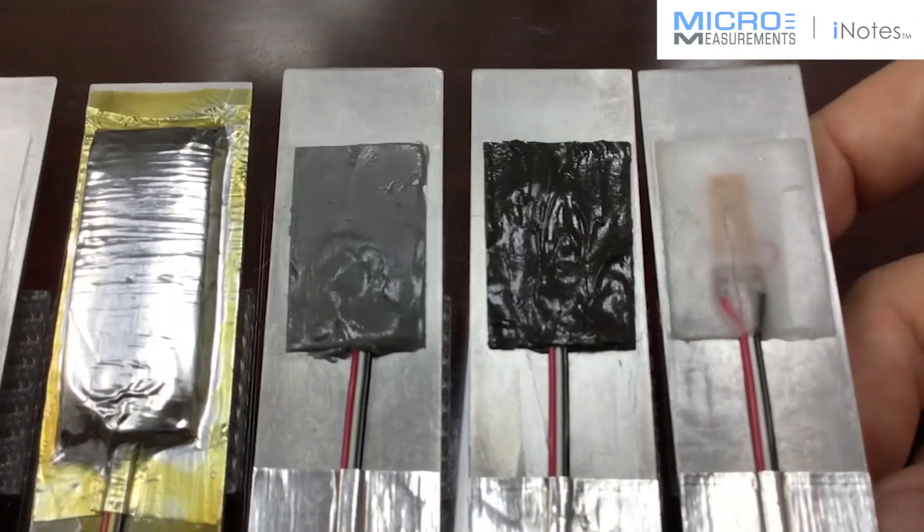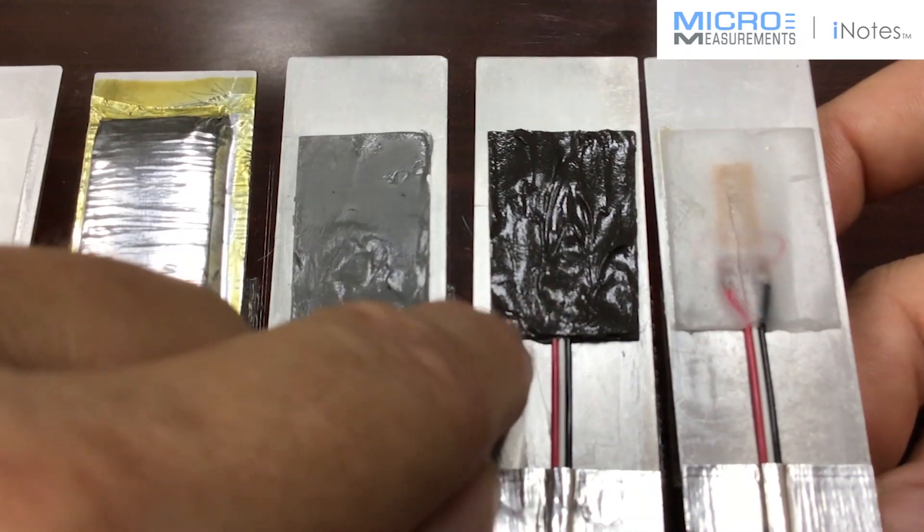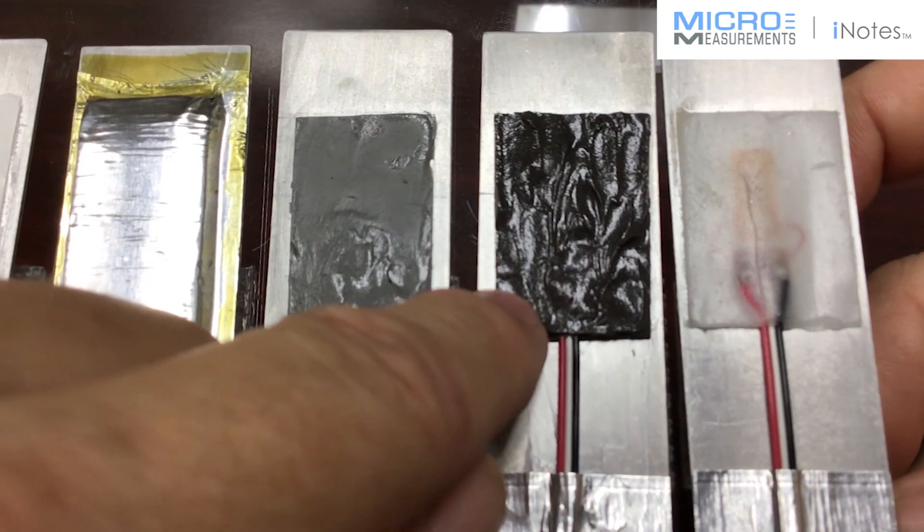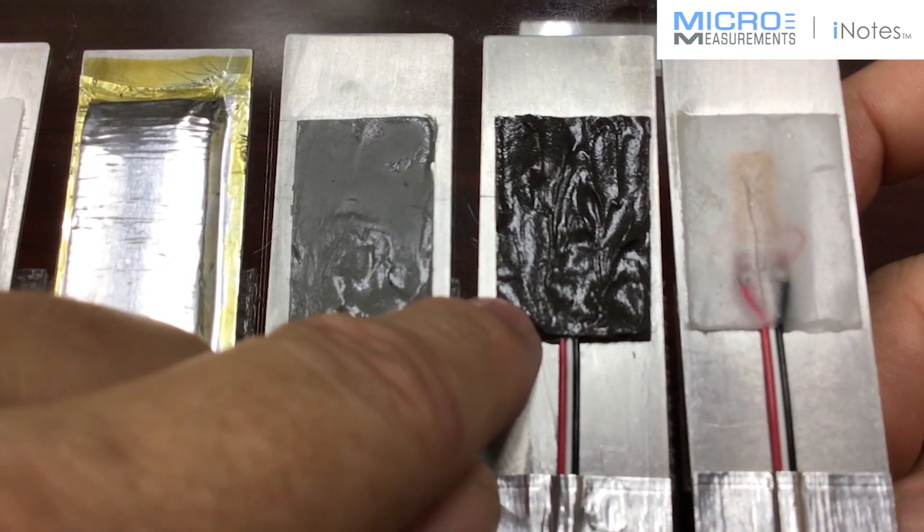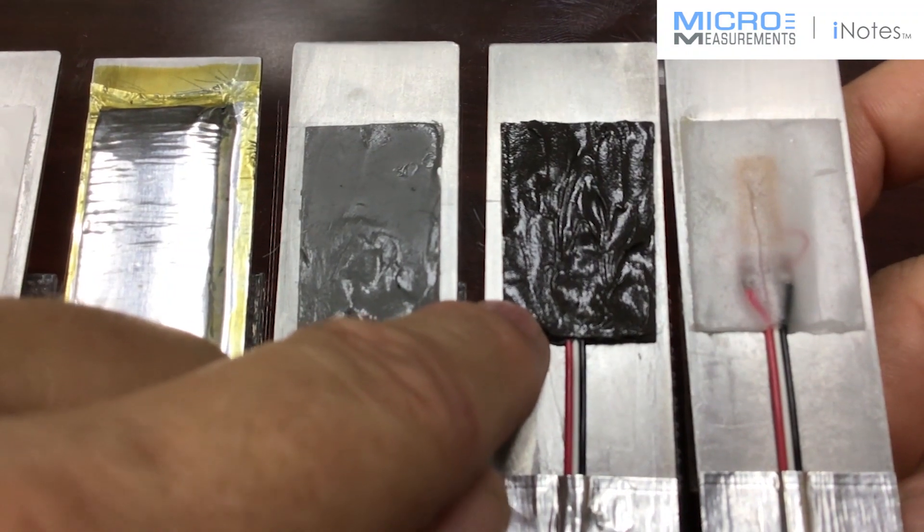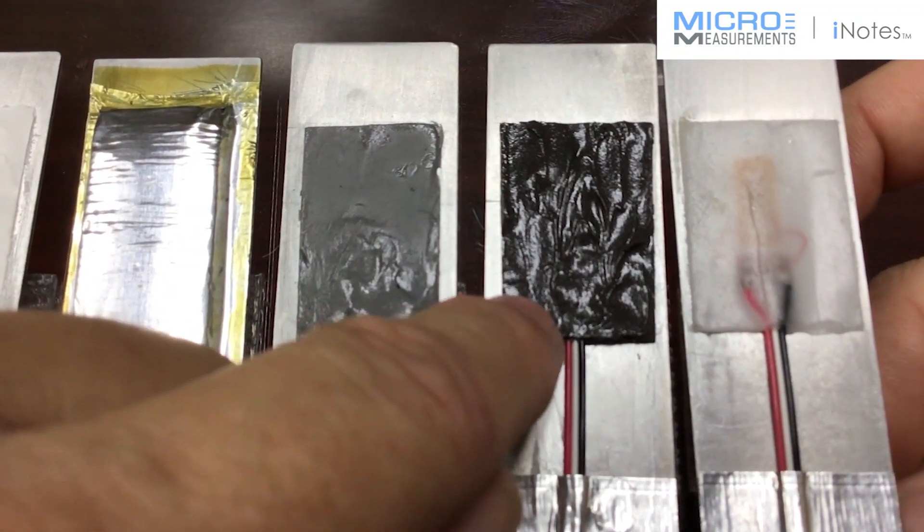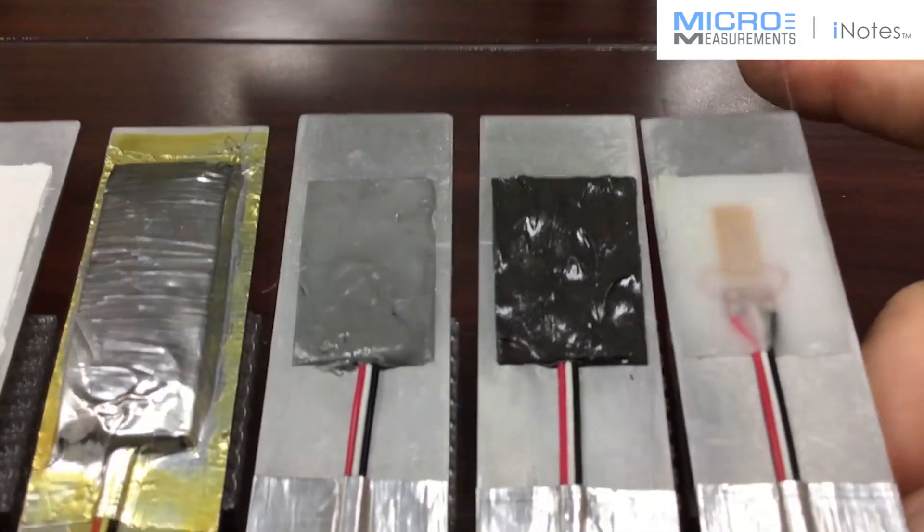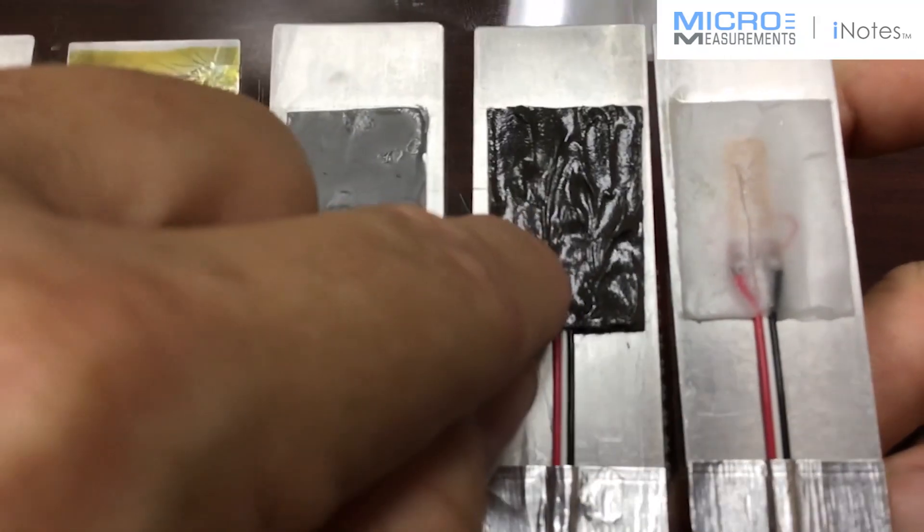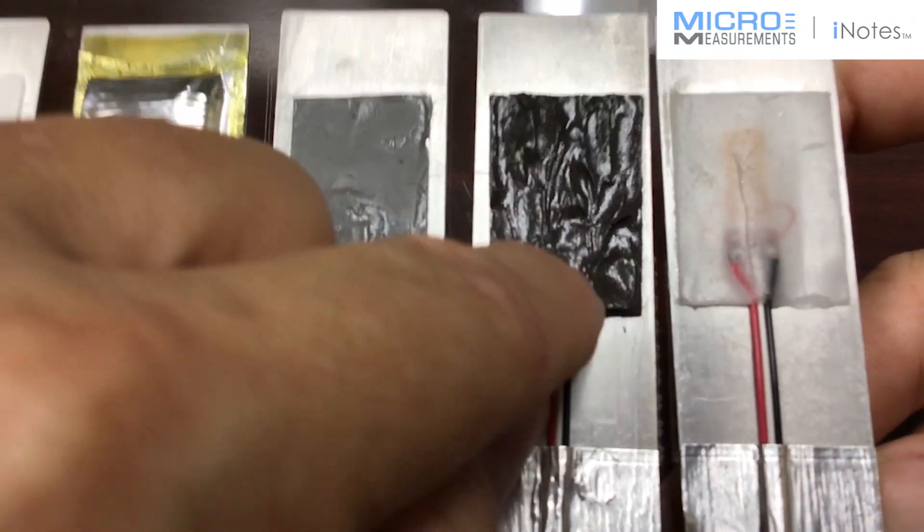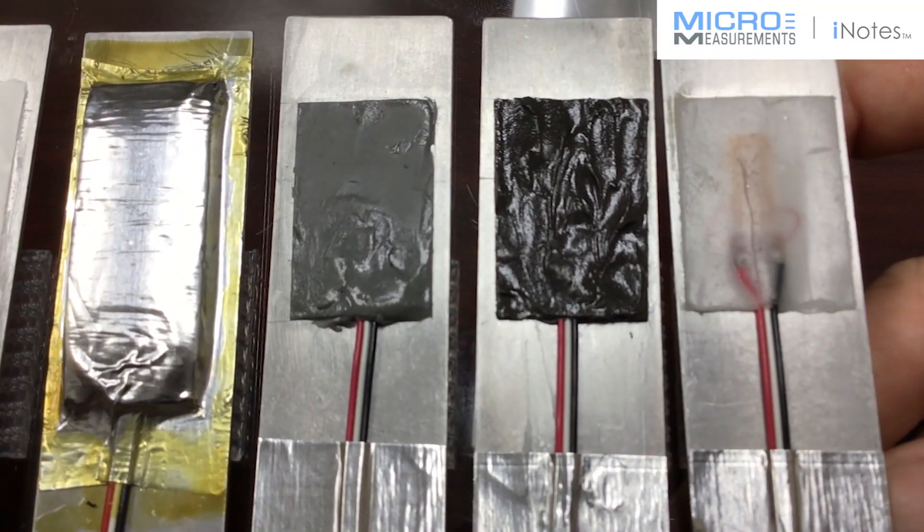And then the next one, this one kind of looks like dark chocolate. This is a two-part polysulfide material we call it M-Coat-JA. It's used out in industry as a fuel tank sealant. It turns out it also makes a very good environmental coating for strain gauges. It's a very tough material. It has the kind of consistency about like the tread on a shoe or maybe a tire. A really tough environmental coating system for strain gauges.